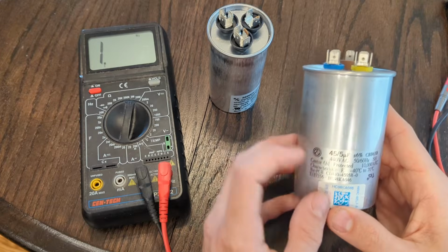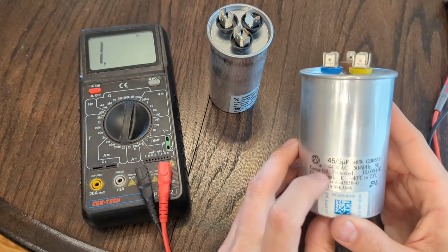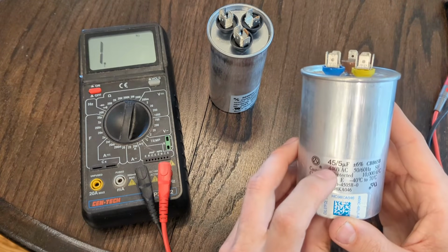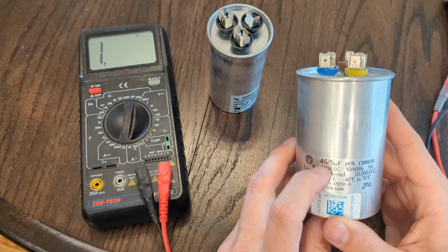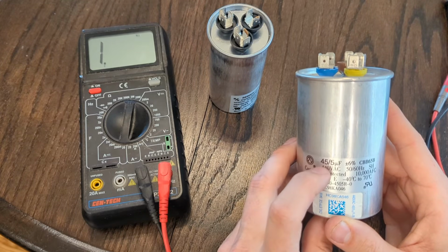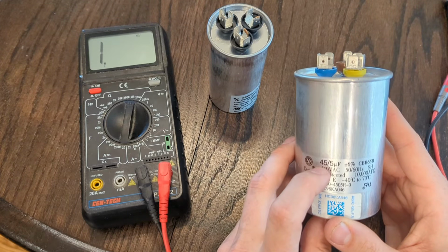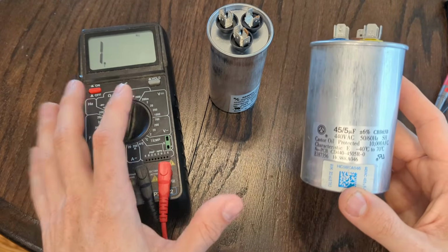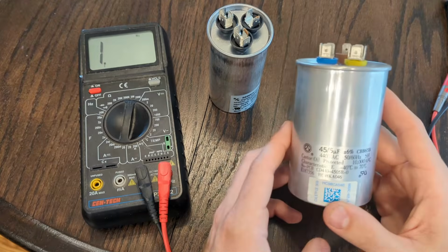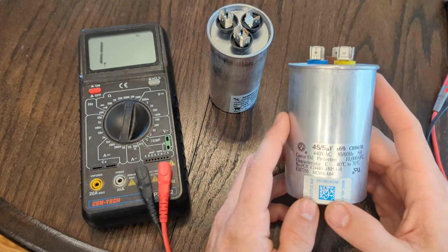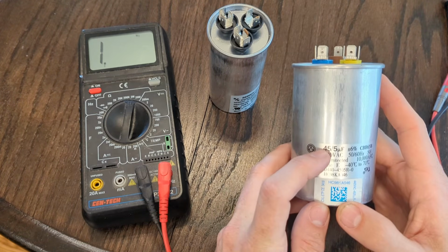Now, if you have one with a specific setting for capacitors, you can check how many microfarads are going through. You want to see it plus or minus 6% of this number, so do a little math. But if you check it on a microfarad rating and it's somewhere in the 30 range, then it is also not going to supply enough power and it's failed. So these are two ways you can test it. If you have a standard multimeter, you can do the jump test. If you have a multimeter that reads for capacitors, you can check the actual microfarad reading.